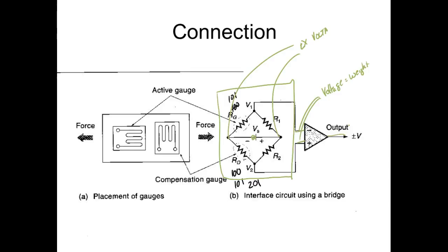The load cell has the Wheatstone bridge built into it. It has four wires coming out of it. Two are for the excitation voltage. That's where you put your DC volts, right? It's got to be a really good regulated power supply, because if your DC excitation voltage changes, then the output of your scale is changing. The other two wires are the actual signal wires.